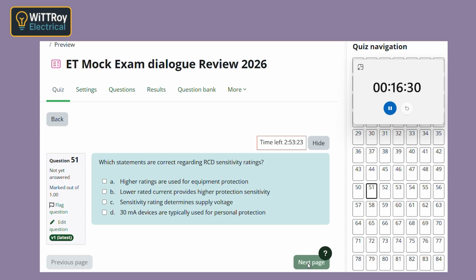Got it. So smaller number means it reacts earlier. Exactly. That's why lower rated current means higher sensitivity. And 30 milliamp is common for personal protection. Yes, that's the typical figure people remember for protecting people from electric shock. What about higher values like 100 or 300 milliamp? Those are less sensitive. They allow more leakage before tripping, so they are usually used for equipment protection or to avoid nuisance tripping.